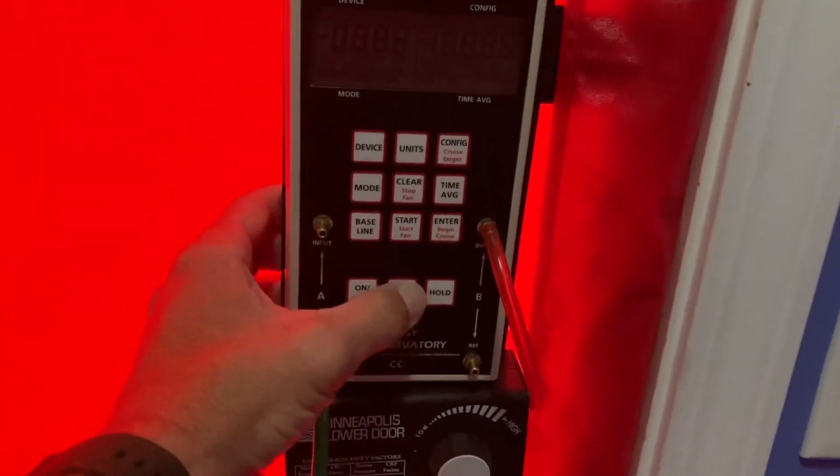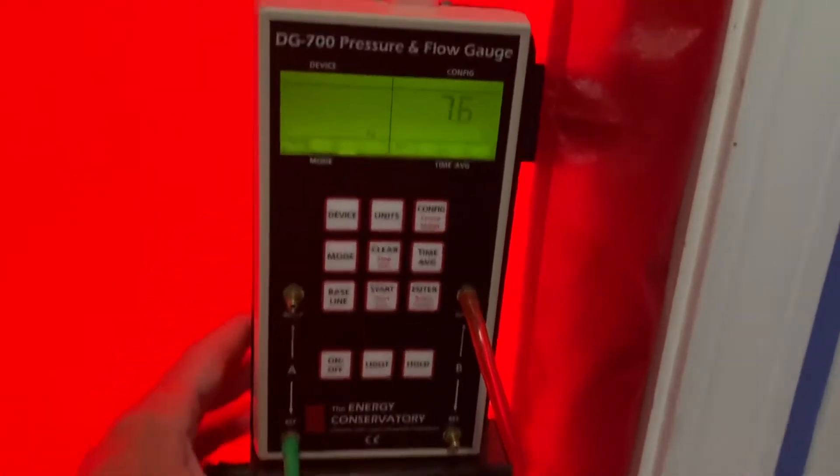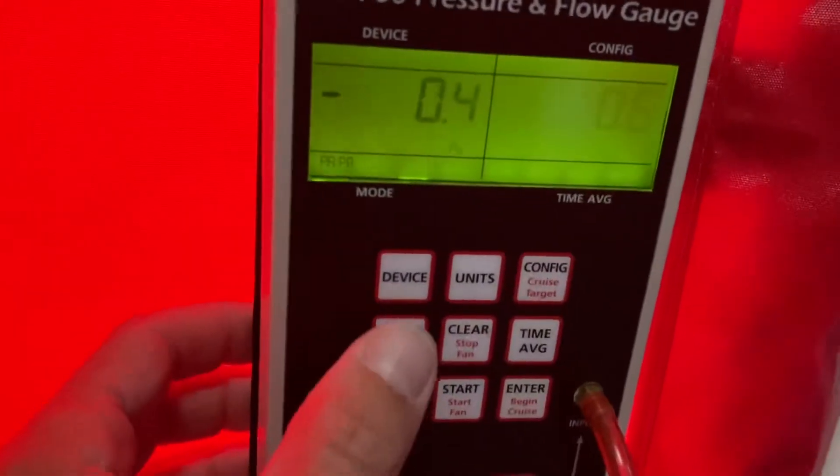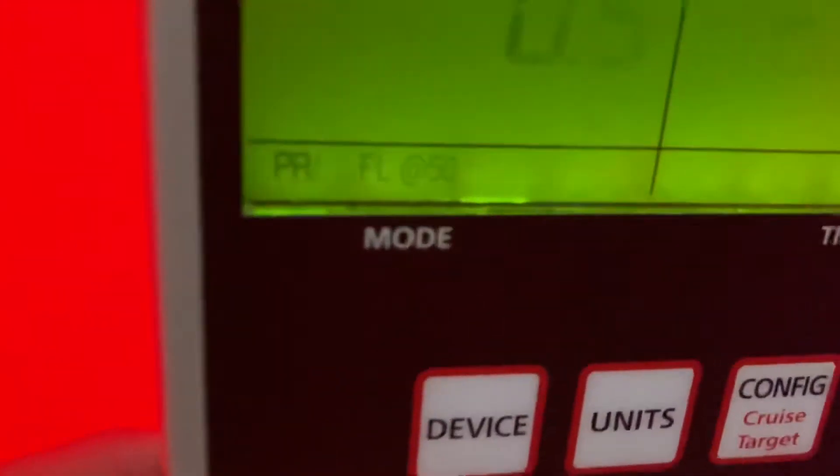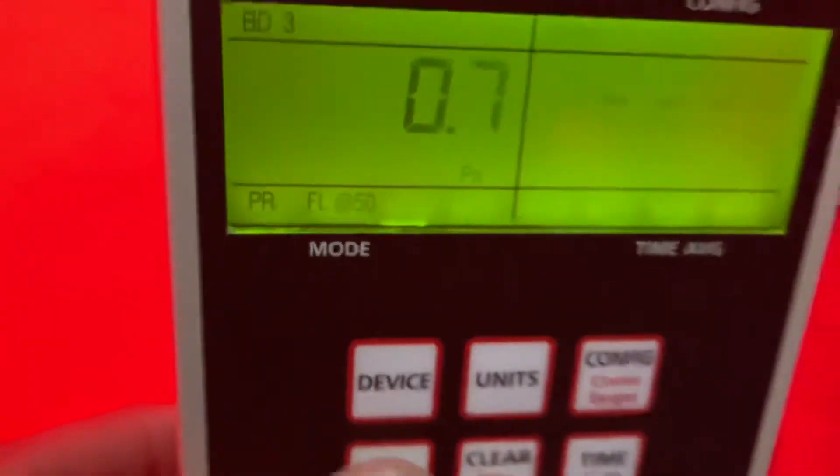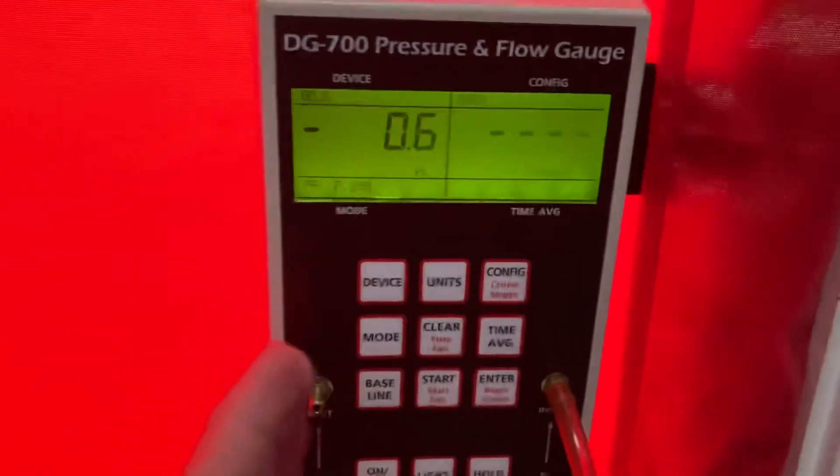From there we'll start turning on the manometer. We're going to hit the on/off button and then we're going to push light—it always helps in these dark homes. Then we're going to hit mode twice. When you first turn it on it's just pressure and pressure. If you push mode twice you'll get pressure on the A channel and flow at 50 on the B, which is what you need.